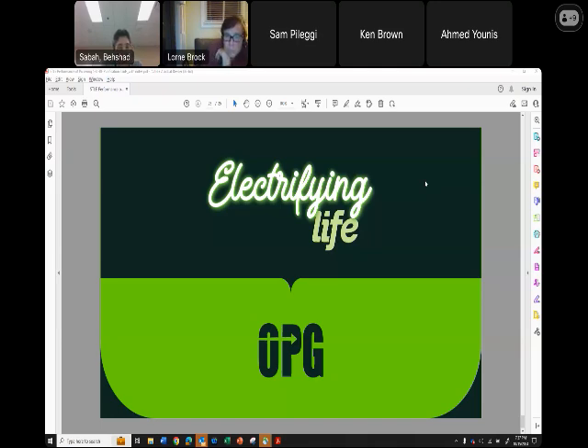So for that question, I did mention that the ABB and Parsons turbines both use the constant volume screw pumps, which, in my opinion, are the major cause of the rapid EHC fluid degradation. With the ABB turbine as well, the tank is very deep and has a small surface area, so the tank retention time is low to allow the bubbles to escape. So ABB has two things going against them.